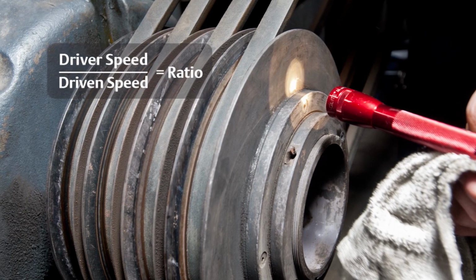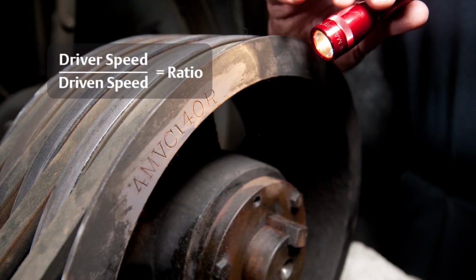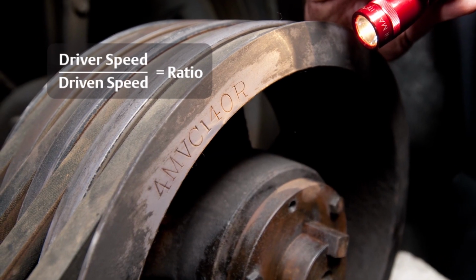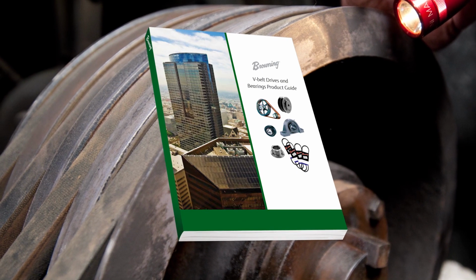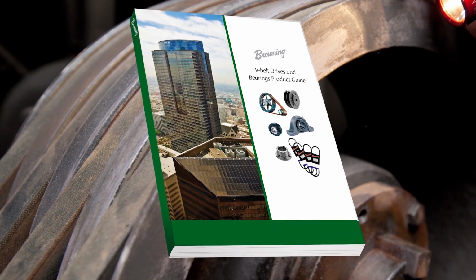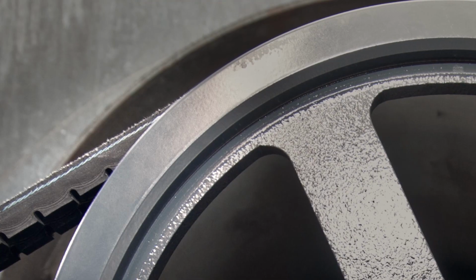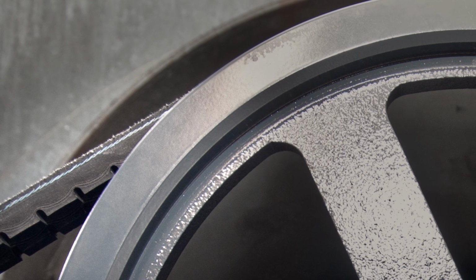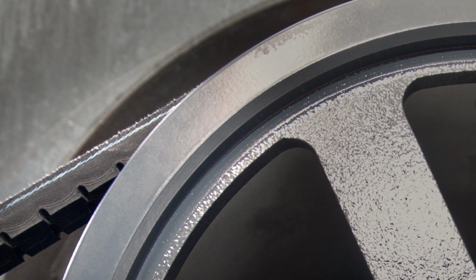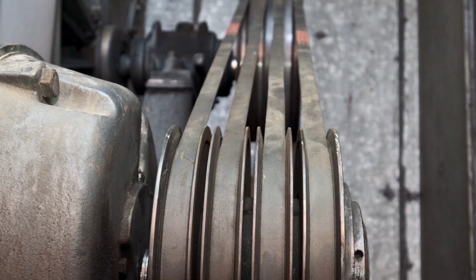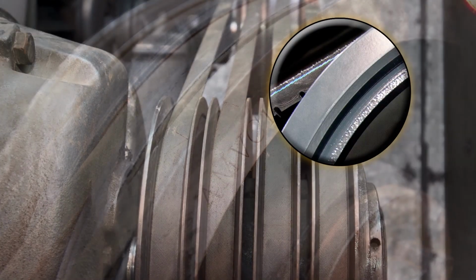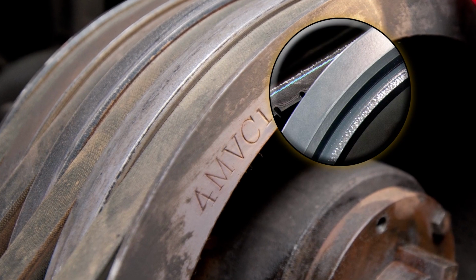To calculate ratio, we need to know both the motor and fan sheave part numbers. With this information, the Browning catalog can be used to determine belt pitch diameter. Pitch diameter is the area in the sheave groove where the belt cords ride. Understanding pitch diameter is critical when calculating drive speed because the cord line is where the ratio and speed calculations are most accurate. Keep in mind, using the actual sheave part number will be the best way to ensure that driven speed remains the same.